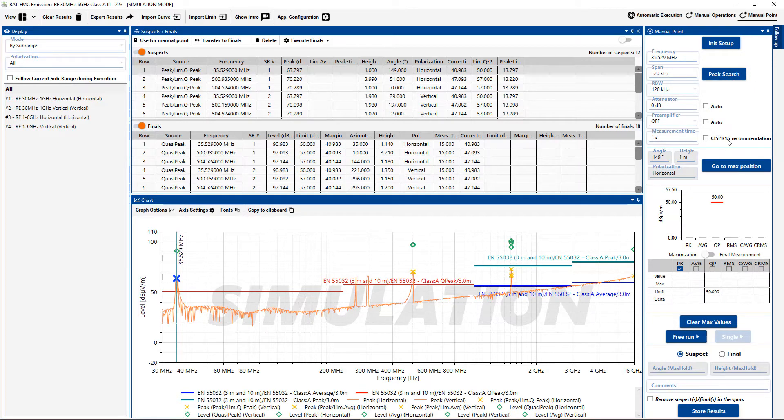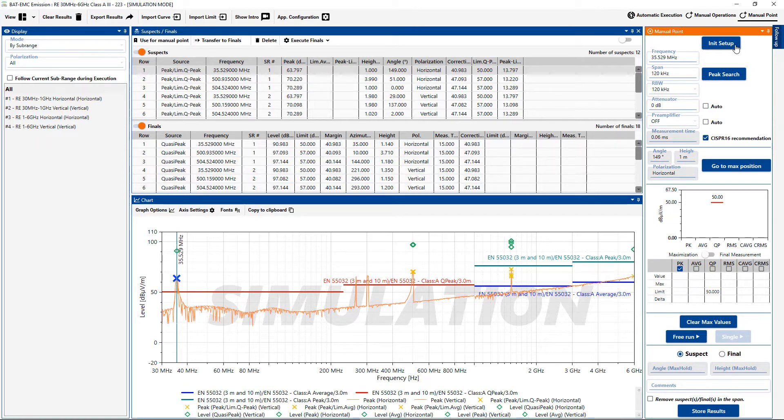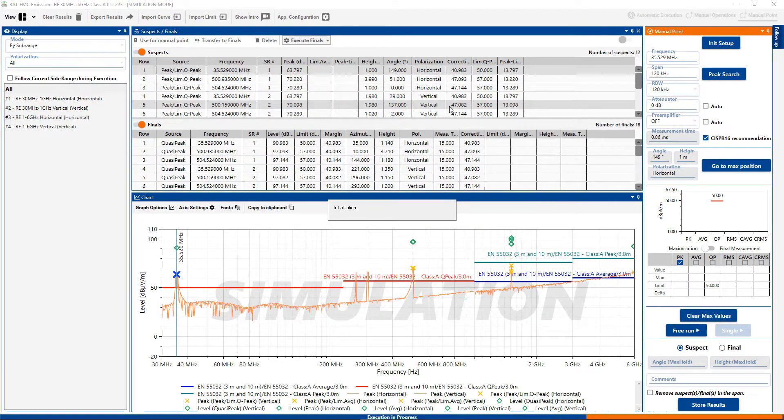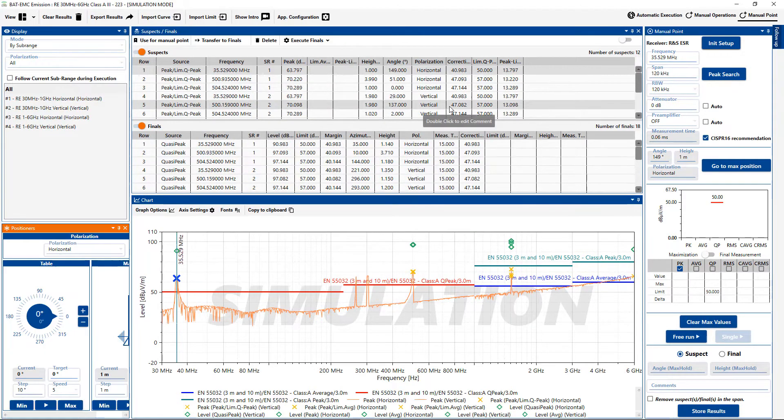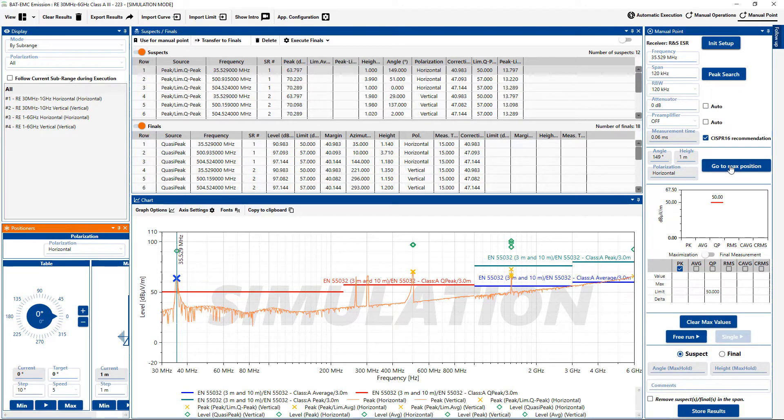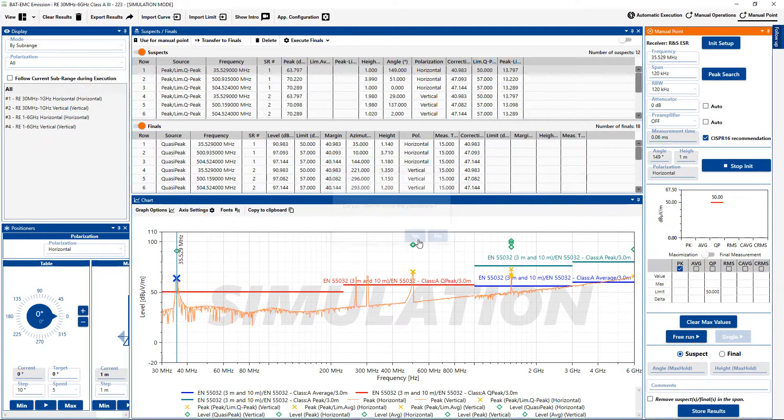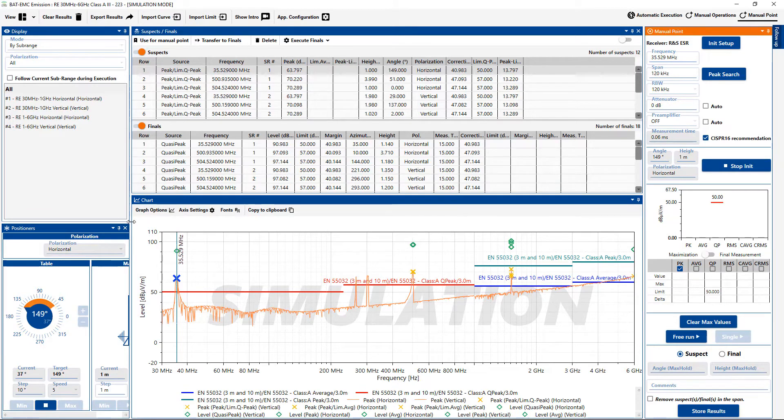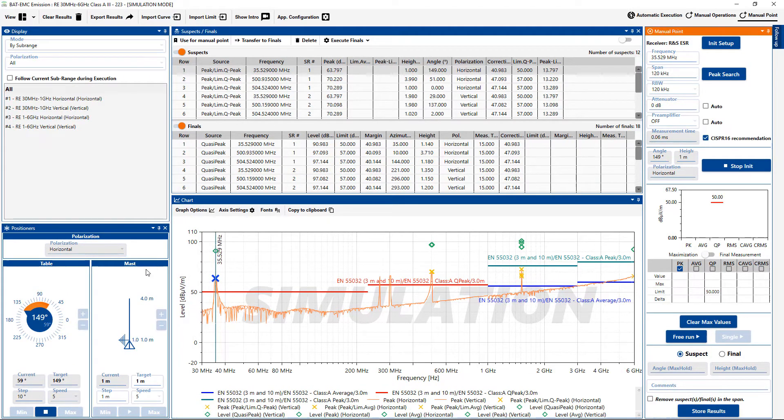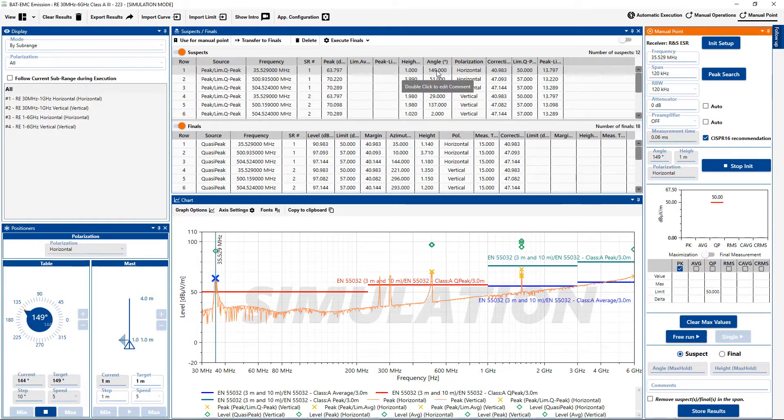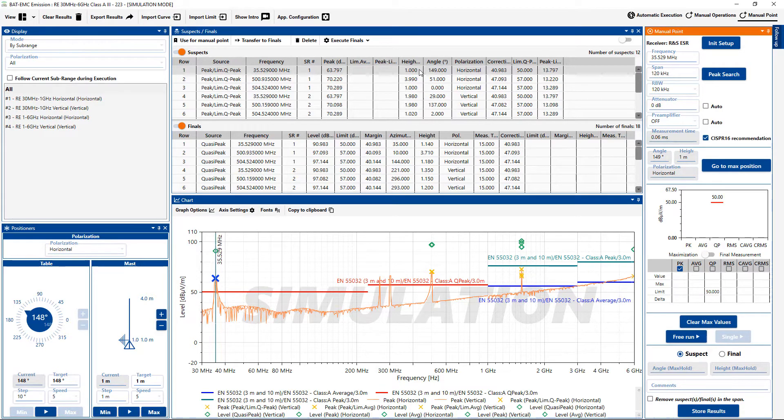So I will choose the CISPR recommended settings because this is a CISPR test. I will initialize the setup. The block diagram appears just to verify the right resources are chosen. Then I can go to the max position that was found at the original scan. So I will say go to the max position. I can enlarge this window a little bit so we can see the position better.